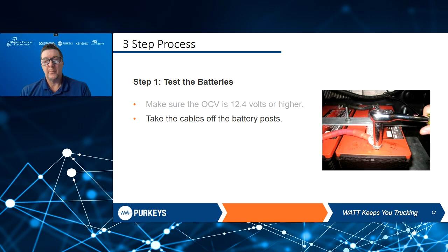Part of that is making sure the open circuit voltage was high enough to do the test. We got to take all the cables off. There are electronic testers that will allow you to do pack tests, which is great, but I'm still going to say twice a year — which is why we always do this as our get ready for summer presentation, and we do one in the fall for get ready for winter — same rules apply. We want to take everything apart because not only do we want to test the batteries individually, but we also want to make sure everything is clean.